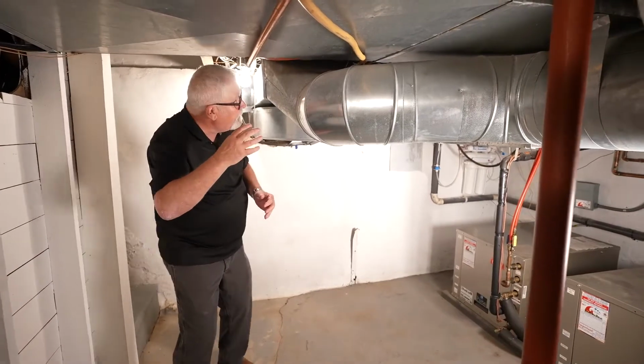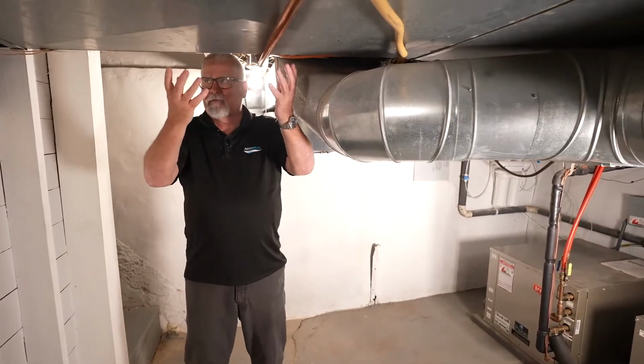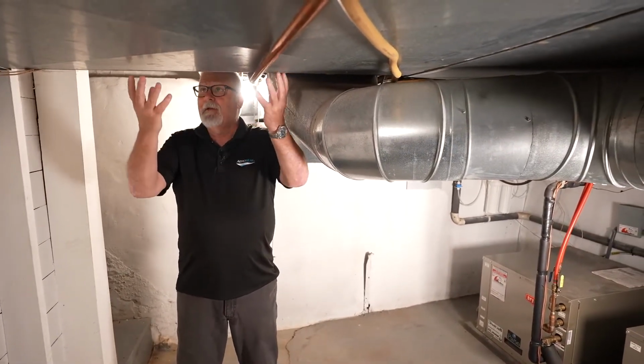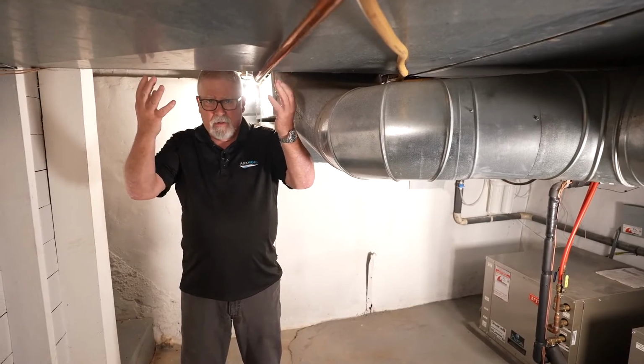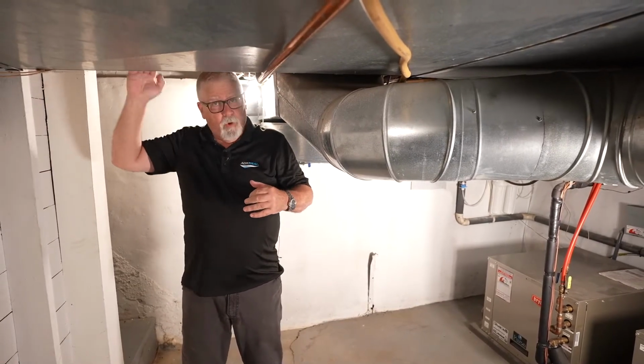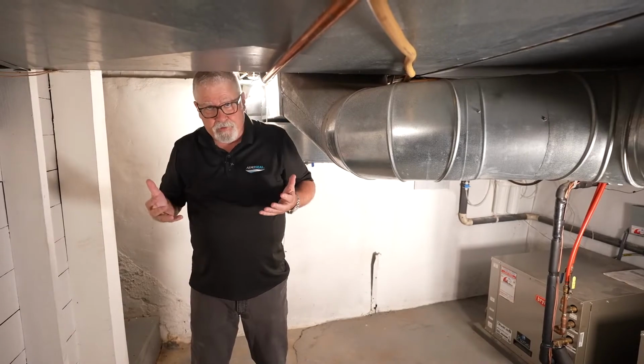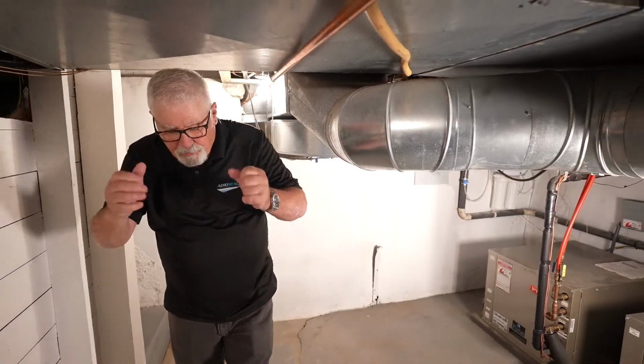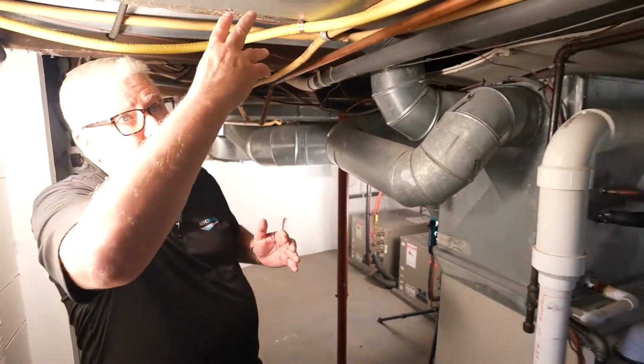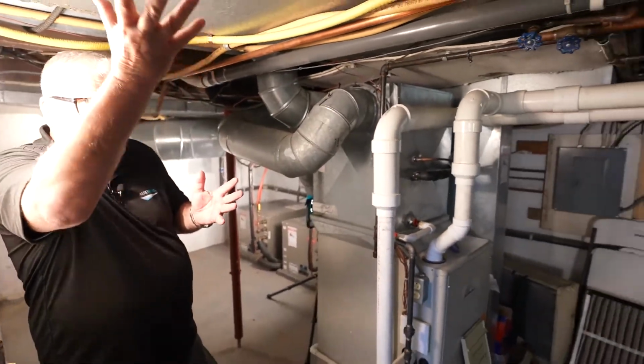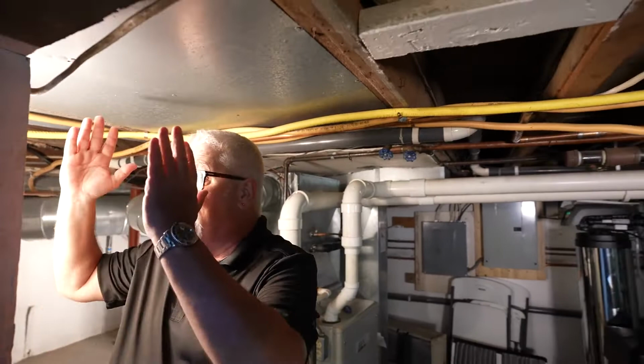I come a little further over, and this is actually a piece of duct, not just a panned joist bay, hanging down below with a couple spots opened up above it where air is supposed to drop down. But as I go back this direction, you'll see actual panning material, sheet metal lining across the top here. It goes back down this wall, and as we said, sheet metal pan returns actually do leak.